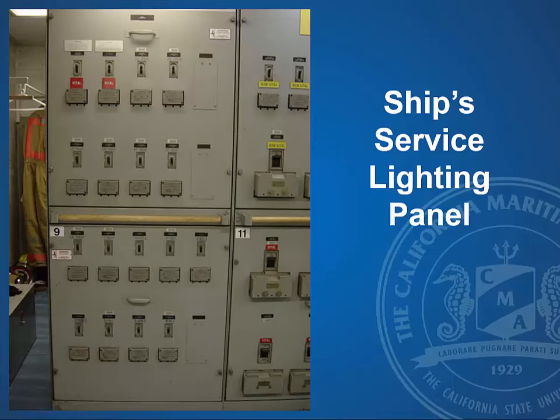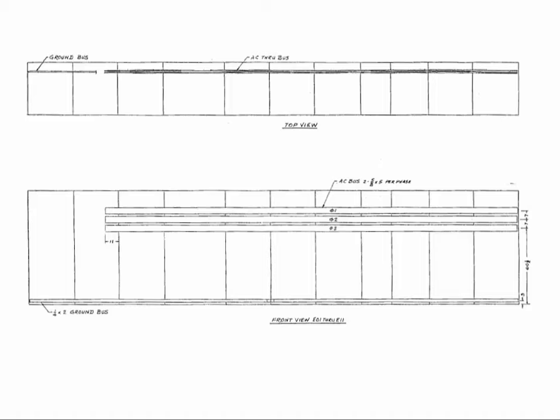So here's your ship service lighting panel. Again, this is on the far left-hand side. The power comes off a circuit breaker, one of the molded case, somewhere down in this area. I believe it's this one here that goes to a transformer. It is dropped from 440 volts down to 115 volts. And then that has actual bus bars in the back of this. And this distributes the power to all these 115 volt circuit breakers, which are feeding different power panels, lighting power panels throughout the ship.